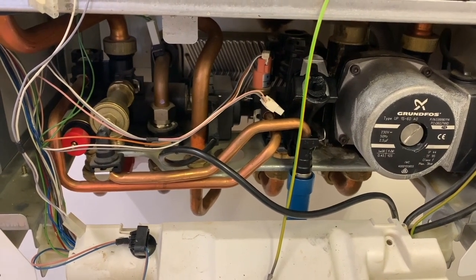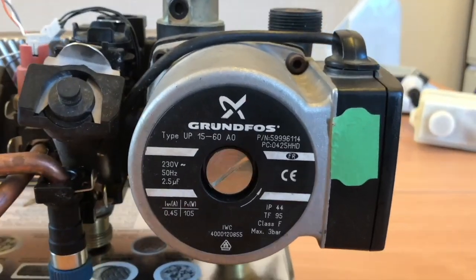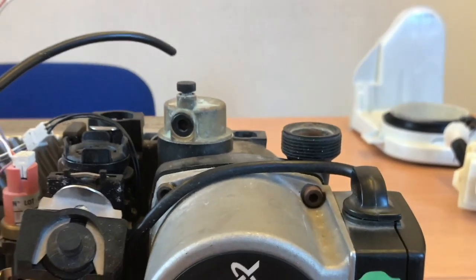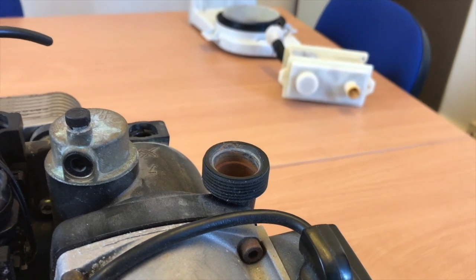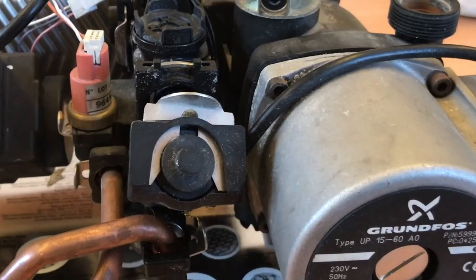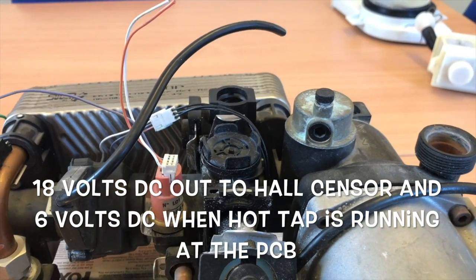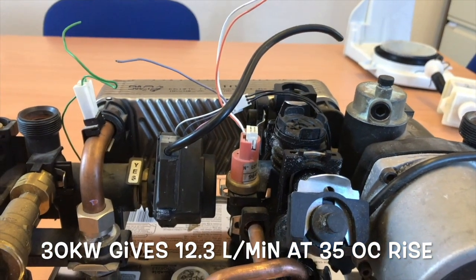We'll use this water set taken from a previous boiler. The pump is a 1560, meaning it's a 6-metre head pump — a 1570 would be 7-metre head. The pump is held on with four Allen screws, two at the top and two at the bottom. Just behind is the connection for the return pipe going from pump to heat exchanger. To the left is the automatic air vent, then the cold water inlet pipe with its filter for water coming into the boiler. The filter feeds the flow turbine which operates the diverter valve for hot water. At the back you can see the plate-to-plate heat exchanger — easy to undo but hard to get out of the boiler.